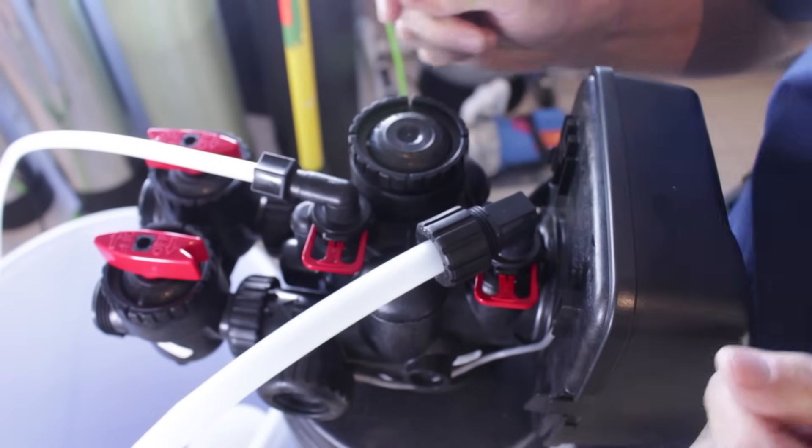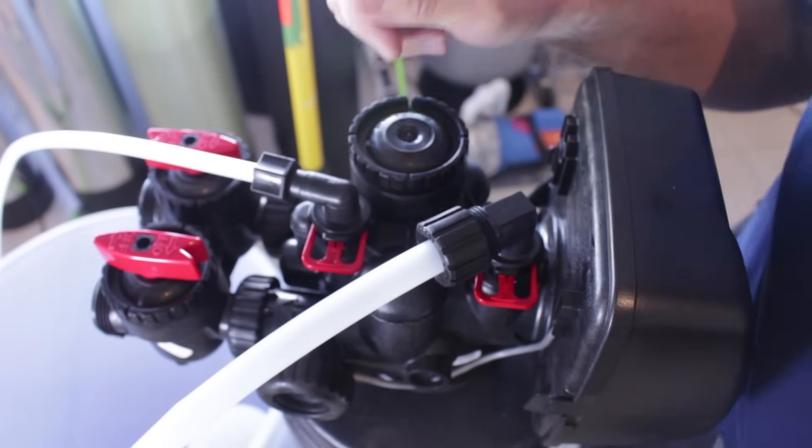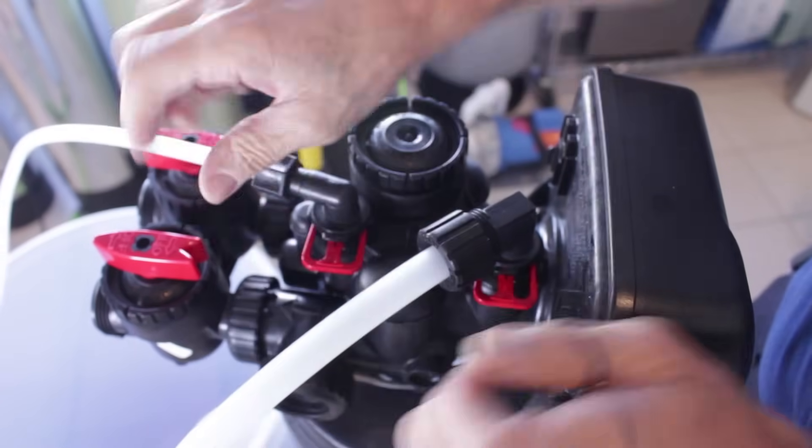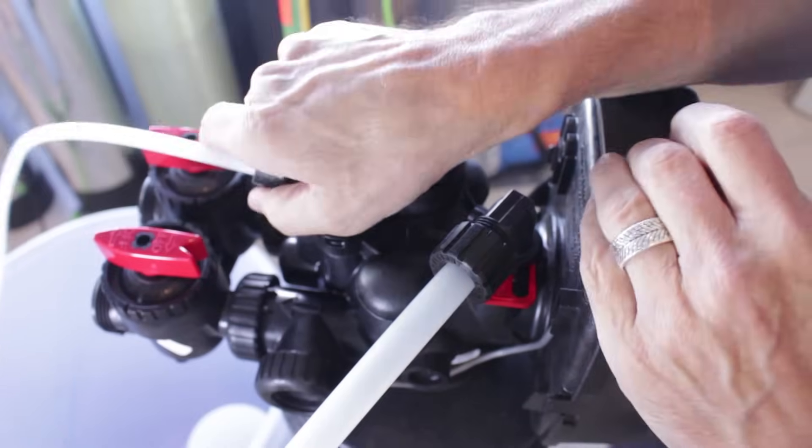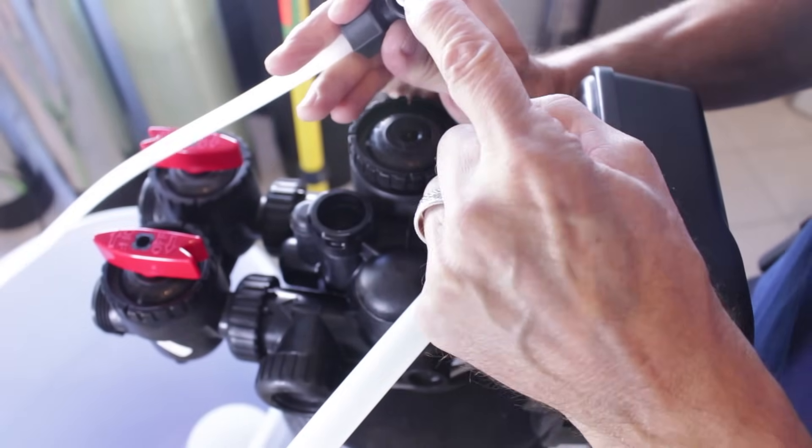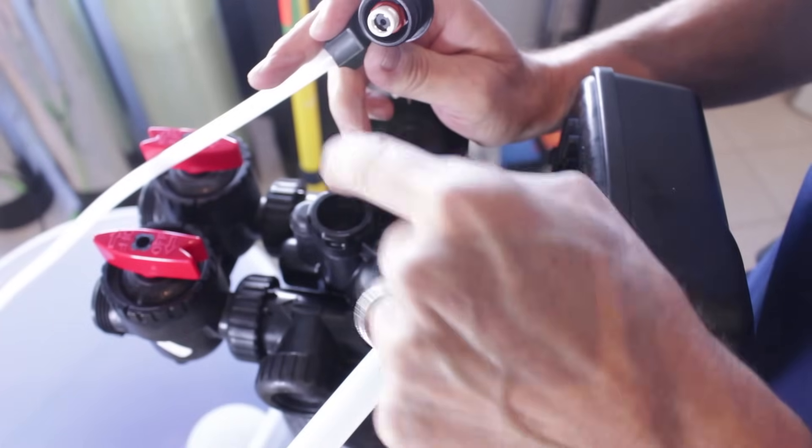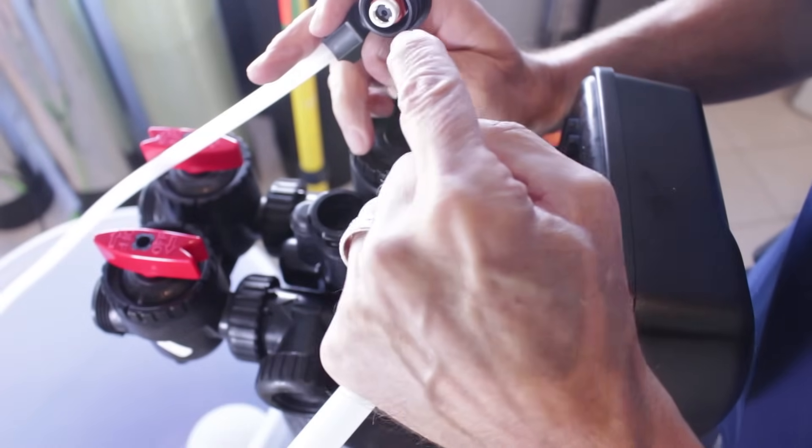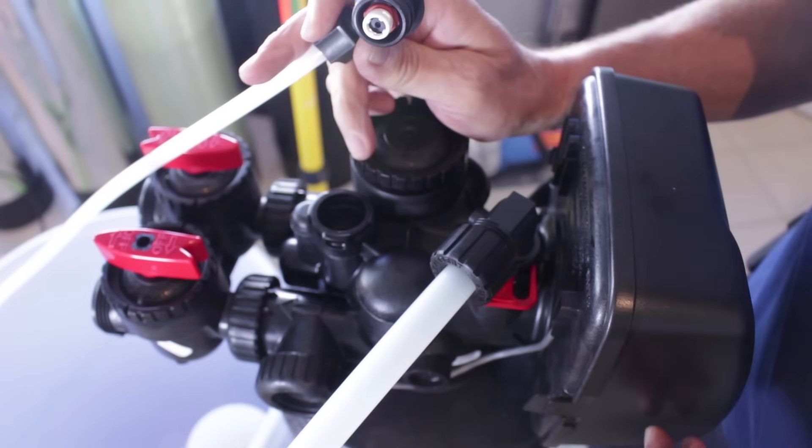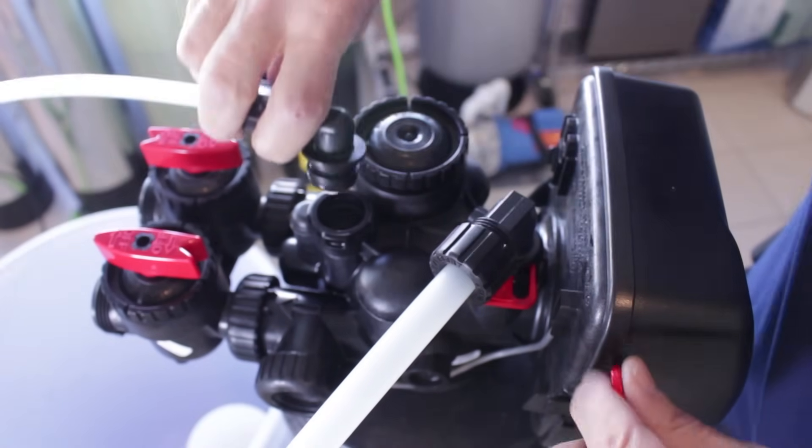The next thing to check is the brine line flow control. That's where the brine line connects to the water softener valve. Right here is the brine line flow control and again it's a very small button. I've seen these where debris inside the brine tank gets sucked up through here and it clogs that little button and then it won't draw brine anymore. Make sure you clean that out.